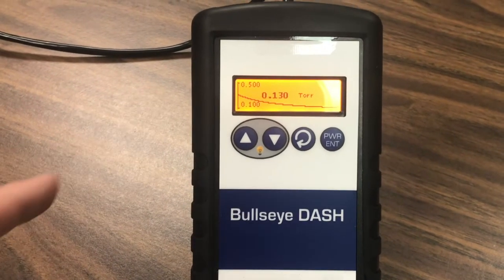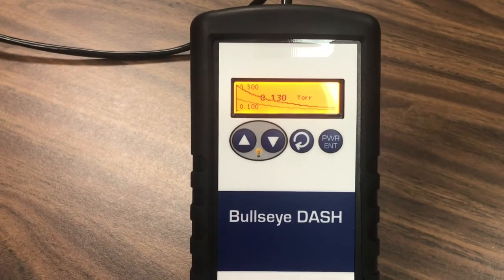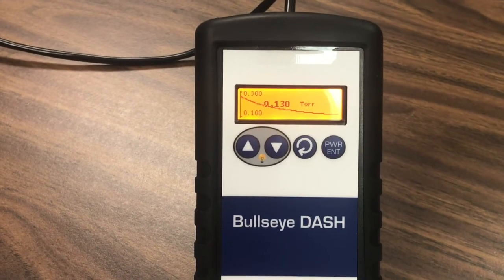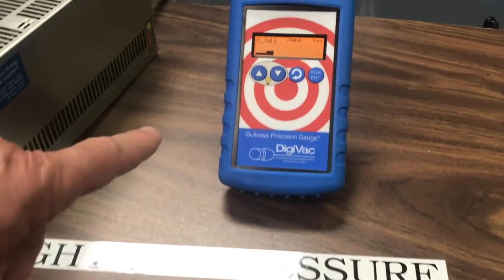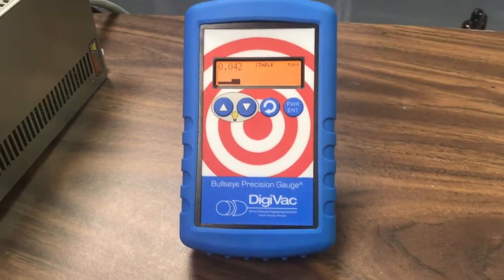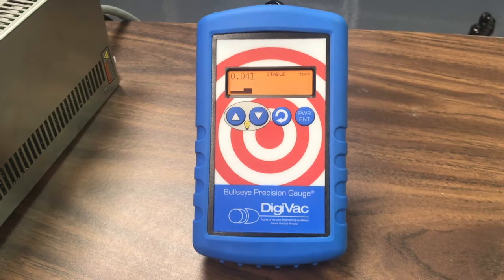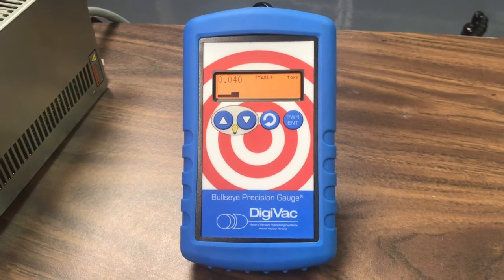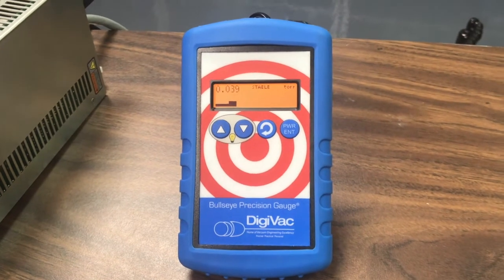Yeah, and this allows me to see vacuum over time. So when I'm looking for that instantaneous blip, this line graph is a perfect thing to see. Whereas here, we're monitoring the inlet of the rough pump. And here I use a bar graph. The reason I use the bar graph is because it gives me this instantaneous view of, hey, what's going on? I'll give you a quick example.